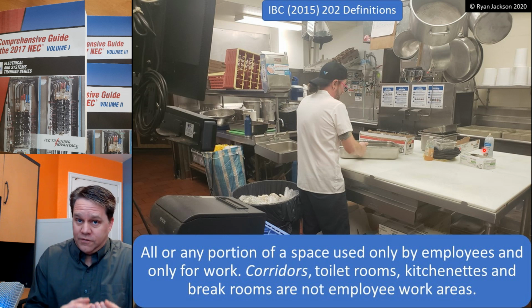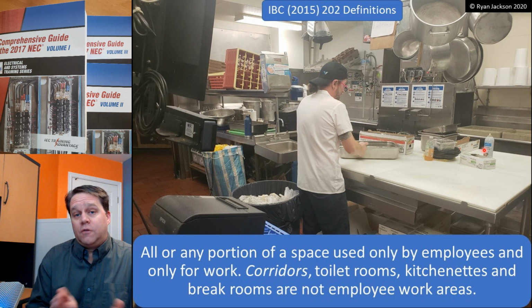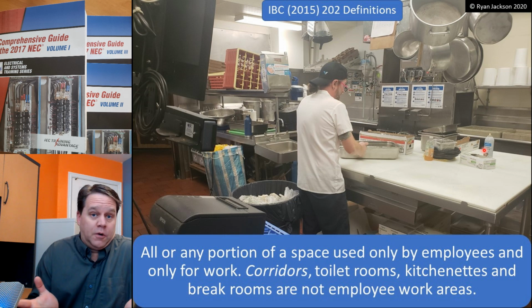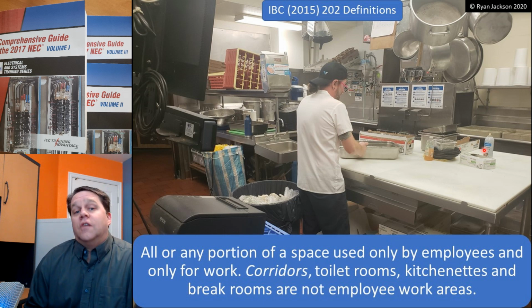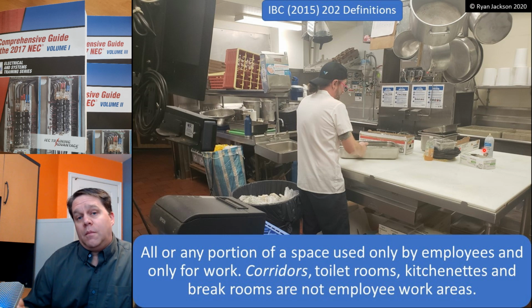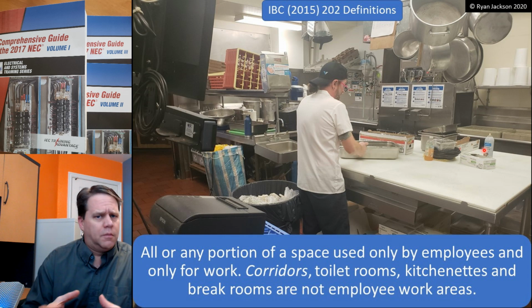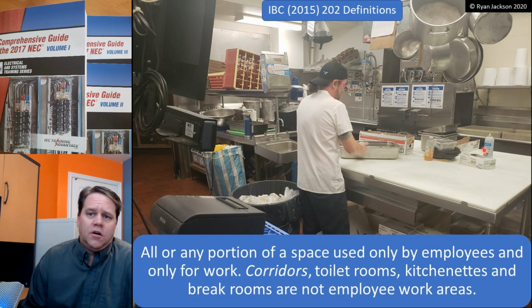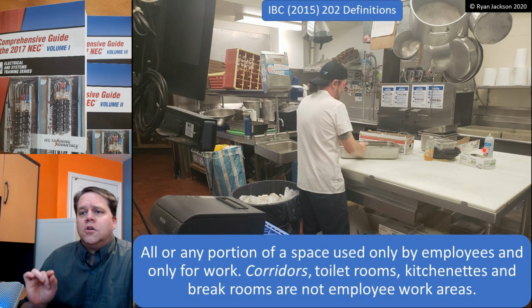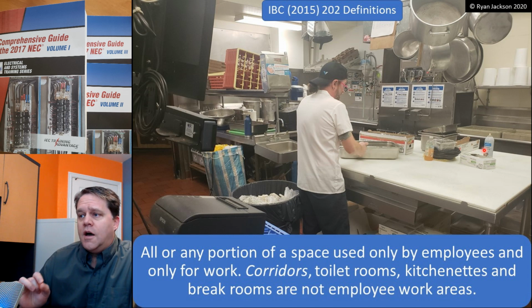Now, it was only for employees, but that was not for work. That was for purposes that were not work-related. So that is not an employee work area. Or if we had a member of the public coming in, we would have a consultation for a building permit question or something. Once the public is there, it's no longer an employee work area. So try not to take advantage of this. It doesn't apply quite as carte blanche as you might think.